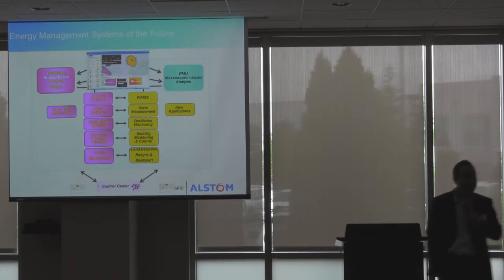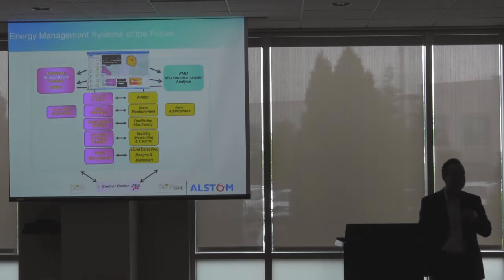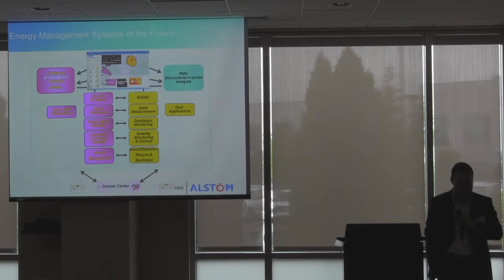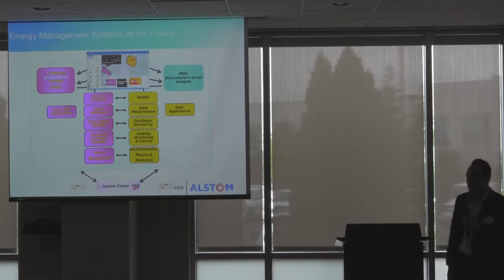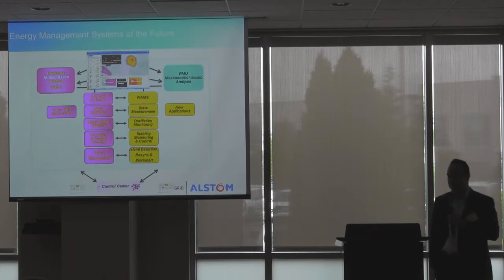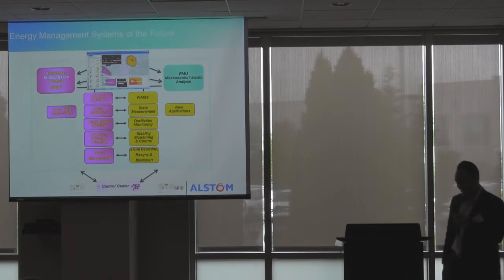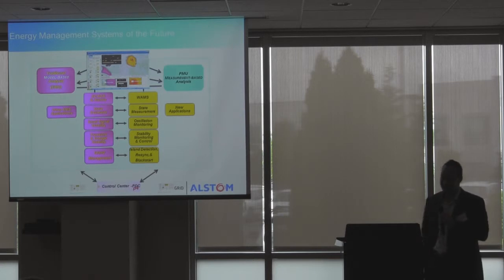Operators in control rooms are comfortable with EMS systems. Recently at NASPI, I went out for dinner with a couple of our customers, and they were telling us that they're bringing in the PMU data. And now that they have 2 voltage measurements, and they're seeing a discrepancy between those measurements, you want to take a guess which one they trust? It's the SCADA measurement, not the PMU measurement.